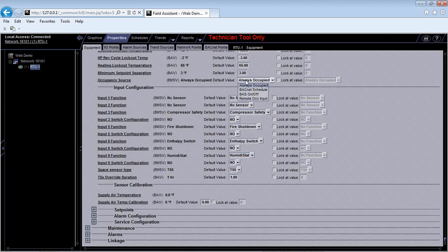The 3 other options you have are Bacnet Schedule. What this is, if I put a local schedule on my controller through Field Assistant, if I went to the Schedules tab up here, it would run off this Bacnet Schedule. Now that schedule is actually writable via Bacnet. So my third-party building automation system could actually write to that schedule and say, Monday you're occupied from 7 a.m. to 8 p.m. or Tuesday you're occupied 7 to noon. That would be one option of controlling when the unit goes into occupied mode.